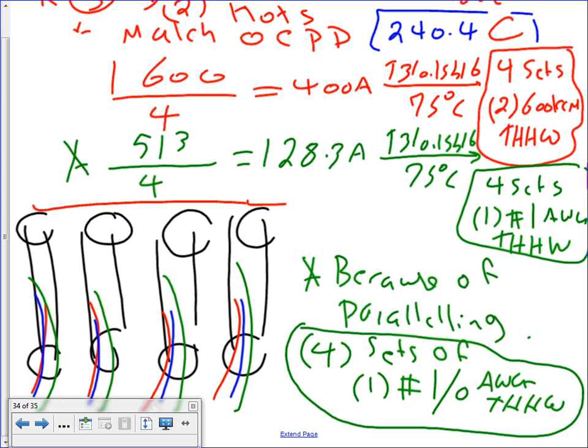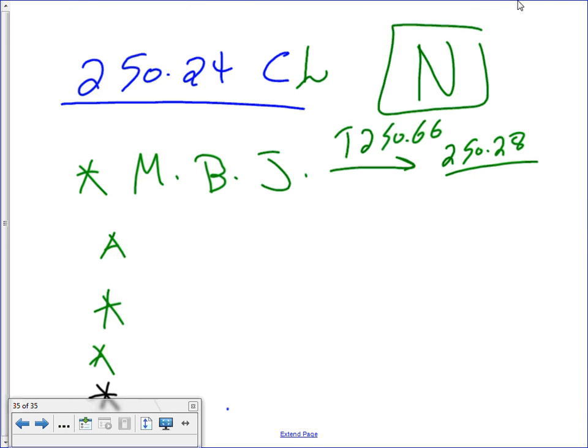So we sized the service entrance panel size, service entrance overcurrent protection device, ungrounded service entrance conductor, building service conductors. So the last one, guys, is the main bonding jumper. I didn't ask you, but it was on the test to size the main bonding jumper. This is how we size it. The neutral cannot be less than the main bonding jumper.